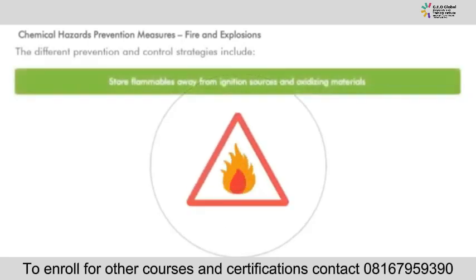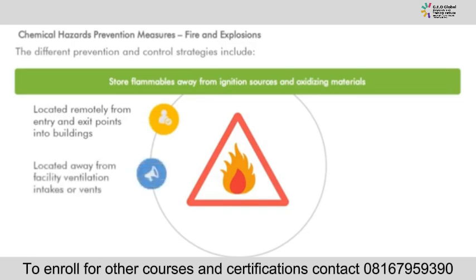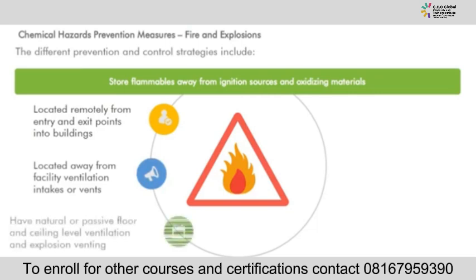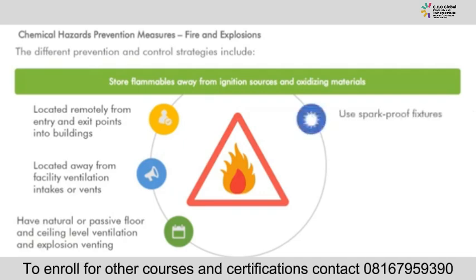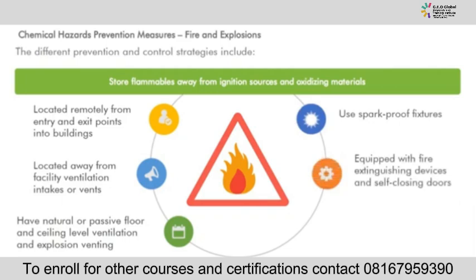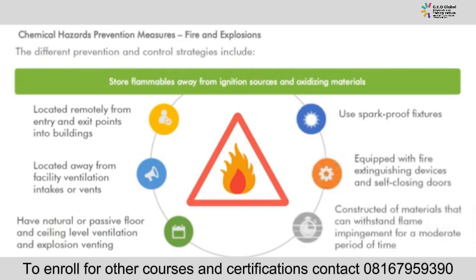The different prevention and control strategies include: the flammables should be stored away from ignition sources and oxidizing materials. The flammable storage area should be located remotely from entry and exit points into buildings, located away from facility ventilation intakes or vents, have natural or passive floor and ceiling level ventilation and explosion venting. Use spark-proof fixtures, equipped with fire extinguishing devices and self-closing doors. Constructed of materials that can withstand flame impingement for a moderate period of time.